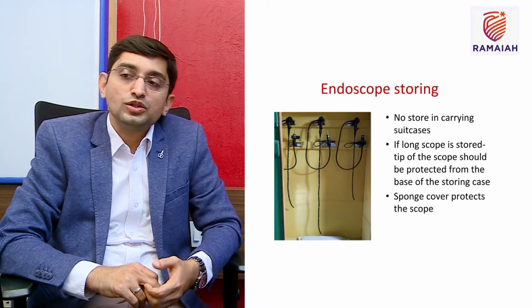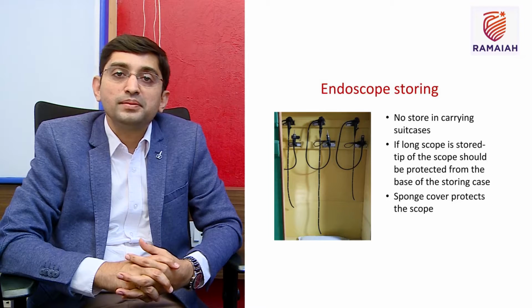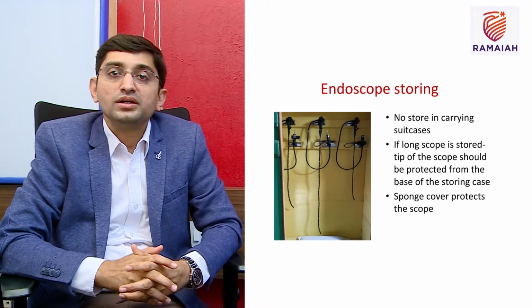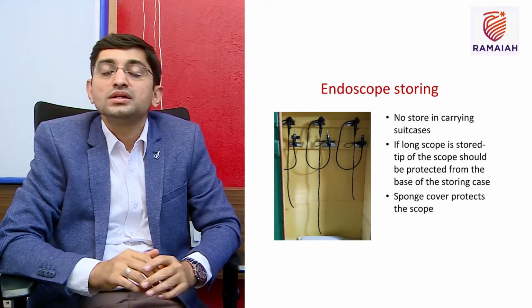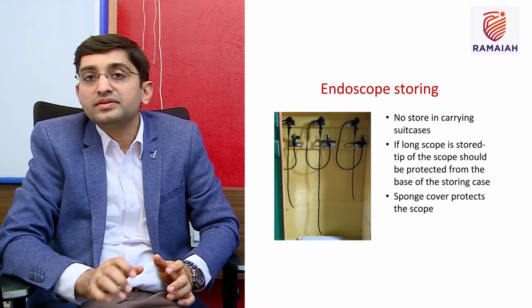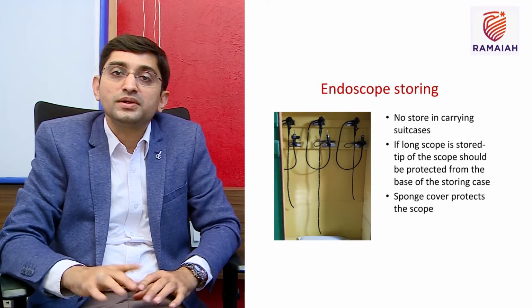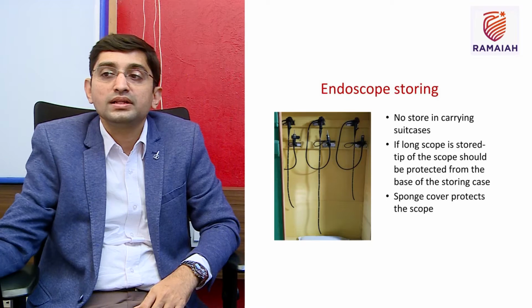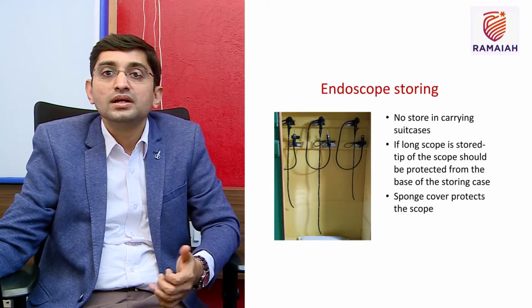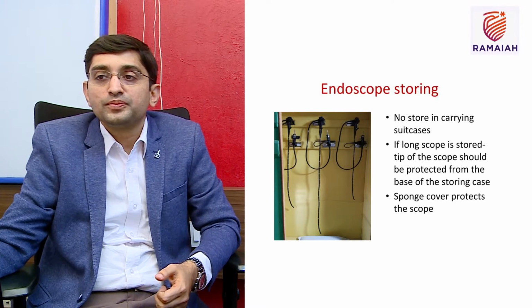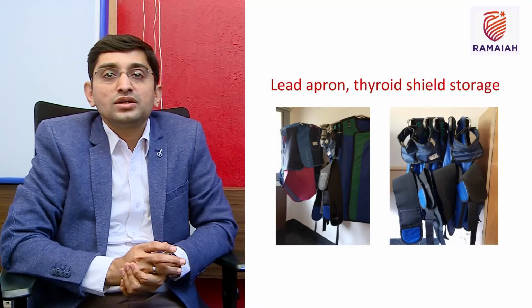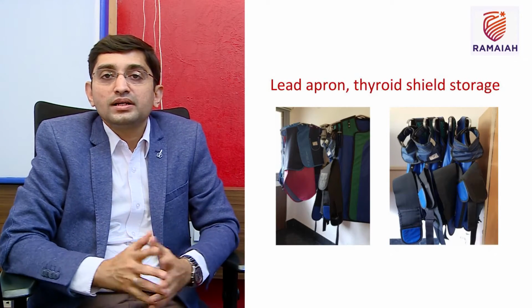If there is a long scope, the tip of the scope should be protected from the base of the storing case. That is very important because the lens, the light source and the air and water port, everything is at the tip. So it's always better to have a sponge cover in case we feel that an assistant may damage the tip of the scope. Lead aprons and thyroid shields should also always be stored properly. They should not be folded and stored.